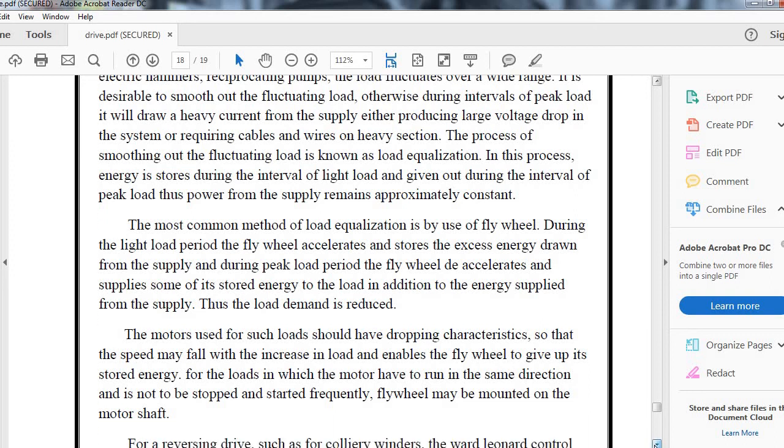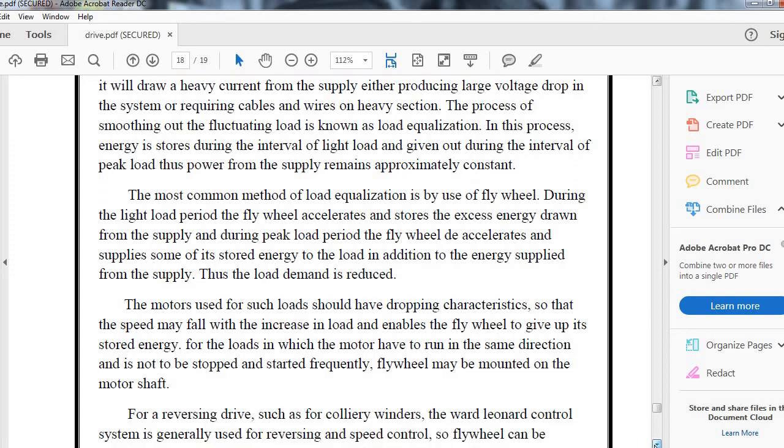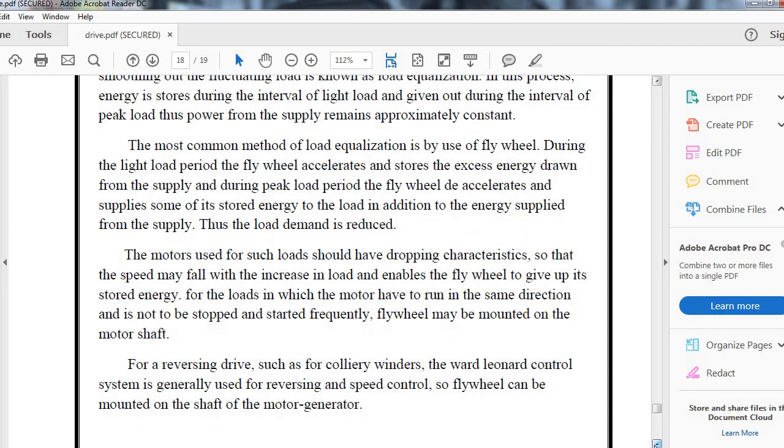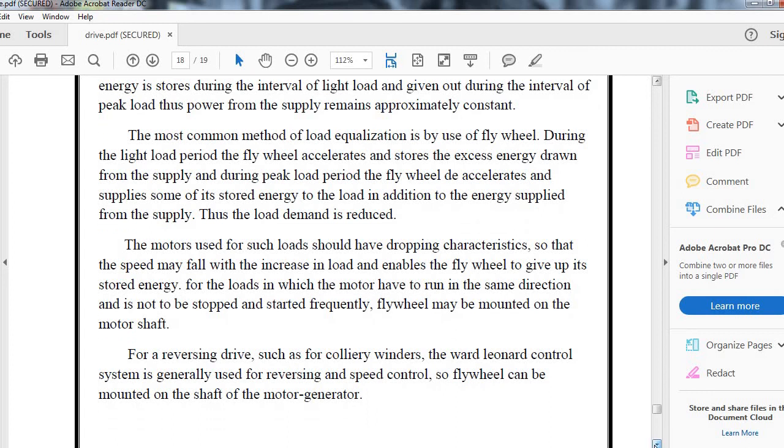Motors used for such loads should have dropping characteristics so that the speed may fall with the increase in load, enabling the flywheel to give up its stored energy.